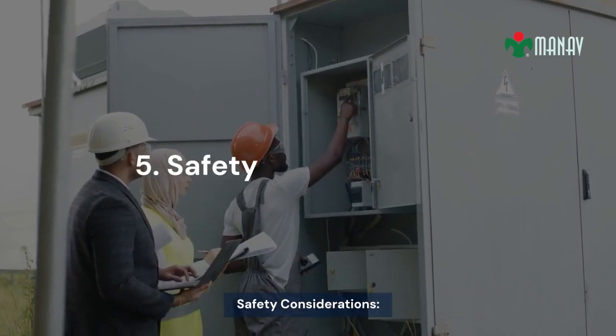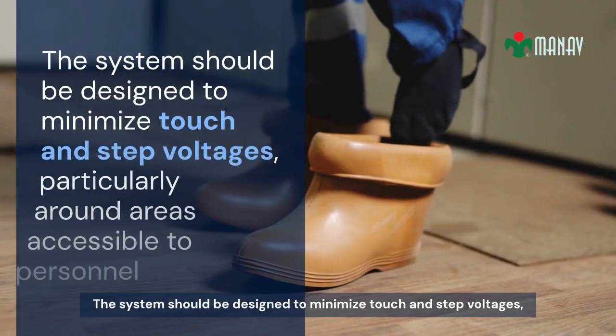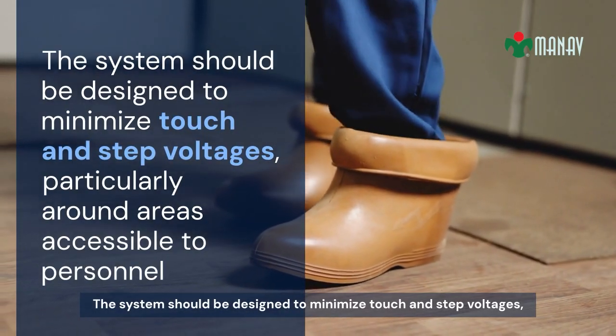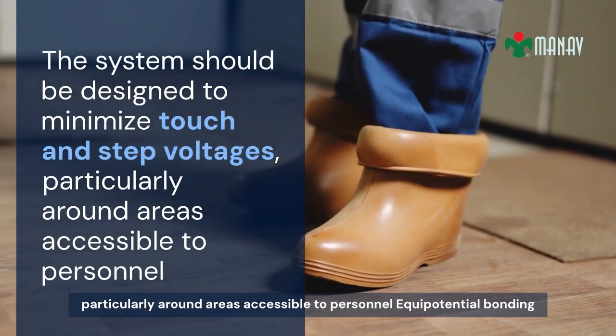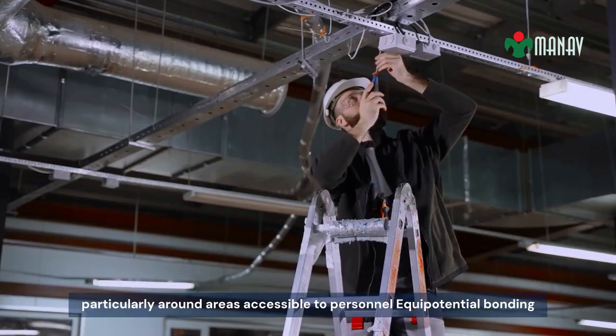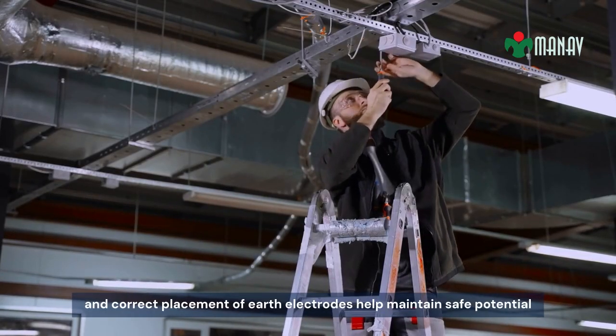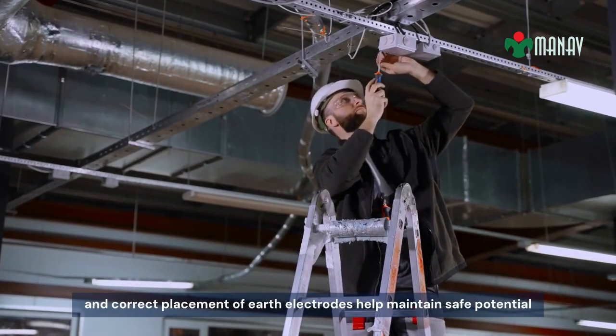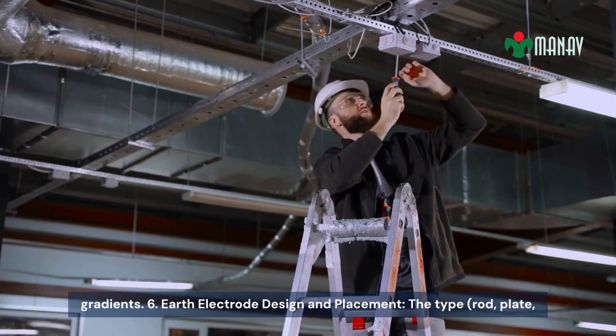5. Safety considerations. The system should be designed to minimize touch and step voltages, particularly around areas accessible to personnel. Equipotential bonding and correct placement of earth electrodes help maintain safe potential gradients.